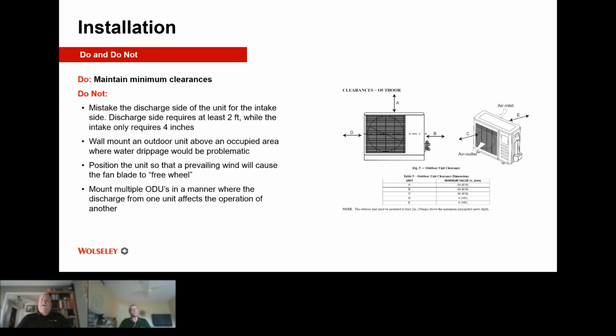We don't want to make the mistake of putting the discharge on the inside of the wall. Personal experience, I have done this in my 30 years, was you do it once, you'll never do it again. And most units are clearly marked on what side is the inlet and what side is the outlet. Don't wall mount an outdoor unit above an occupied area where water drippage may be problematic.